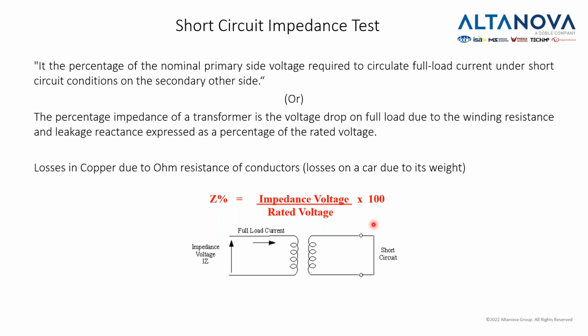I can put it like this. You have copper in your transformer. That copper has resistance. That resistance will cause some losses. We measure the losses in copper with this test. We short circuit the secondary side and increase the voltage on the primary side until we obtain the nominal current on the secondary side. That's the theory. In practice, we don't have to go so high, but this is the number you will find on your transformer's nameplate, and it's marked as Z percentage.